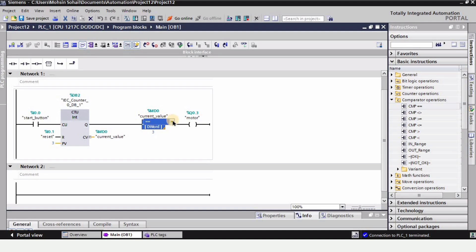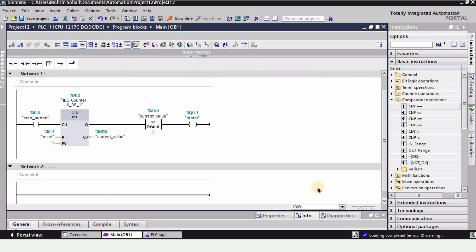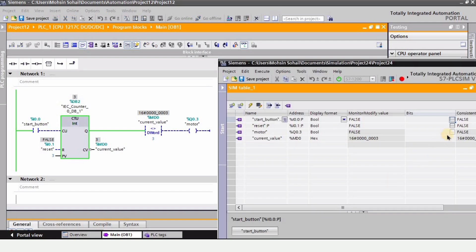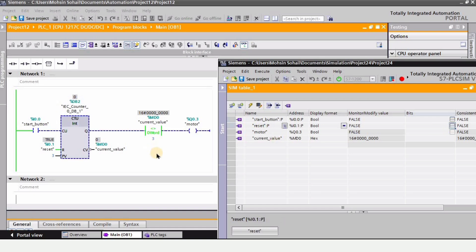Now I'm going to double click and select the Not Equal instruction. You can also place it directly from the dropdown. I'll download it, turn on monitoring mode, and let's see how the Not Equal instruction works. I'll reset the counter first. As you can see, zero is not equal to three, yet the motor is not turned on — that's because the power supply wasn't active yet. But as soon as the counter goes beyond three, for example four is not equal to three, and now the motor turns on.